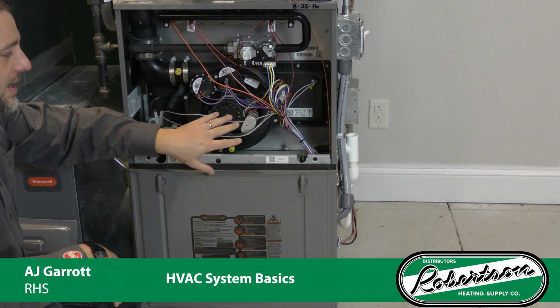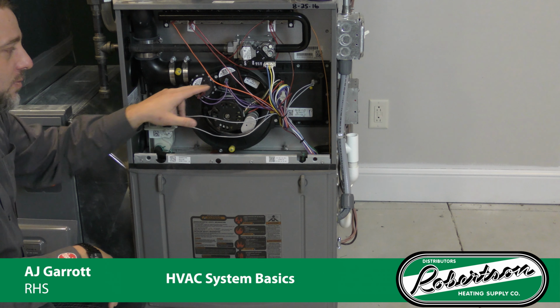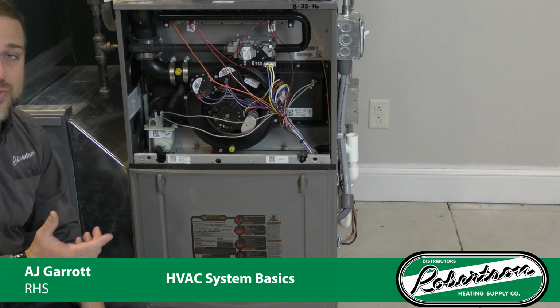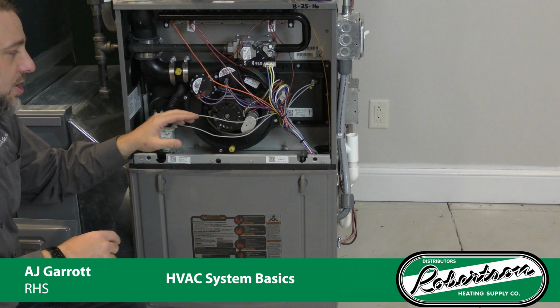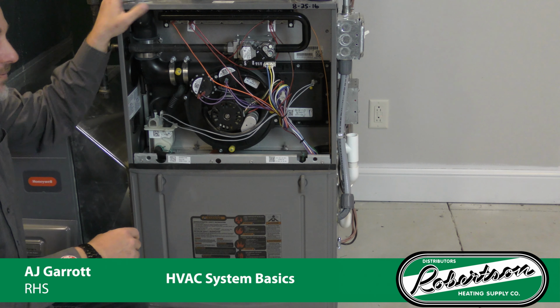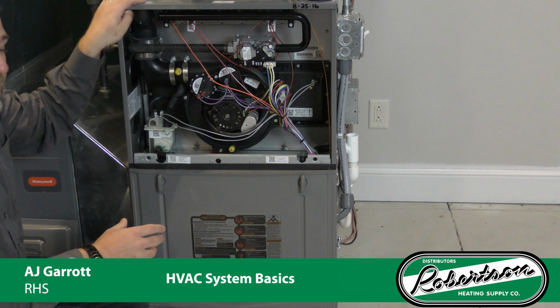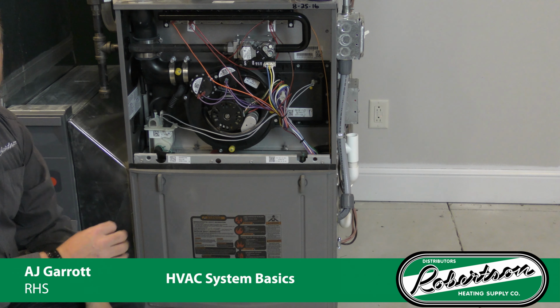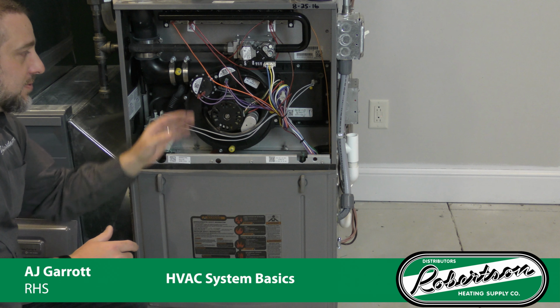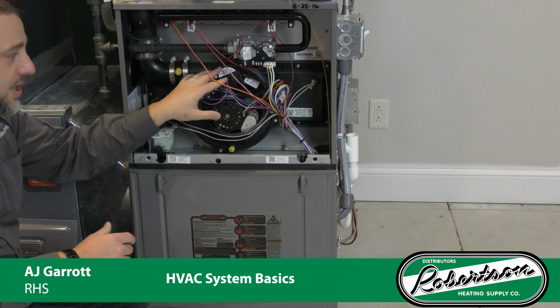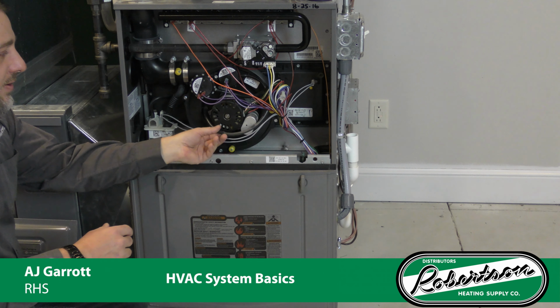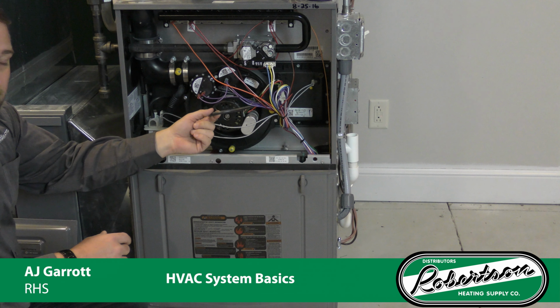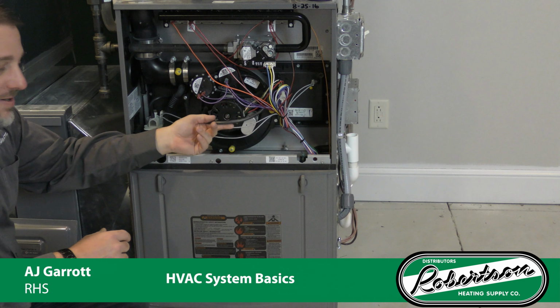On here for that draft inducer, we have 2 pressure switches. The pressure switch's job is to make sure that our flue pipe is unobstructed and our heat exchanger is okay as well. That is the sole job of these little pressure switches here. They actually have a silicone hose that comes and connects into this draft inducer.